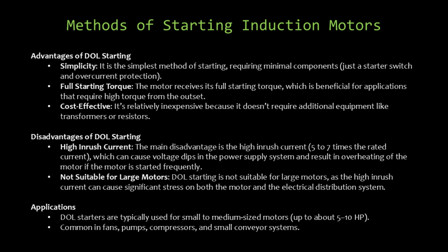However, direct online starting isn't without its drawbacks. The primary concern is the high inrush current, which can cause significant voltage dips in the power supply system. Frequent starts can lead to motor overheating. This method becomes less suitable for large motors, as the substantial current can stress both the motor and electrical distribution system. Engineers must carefully evaluate the motor's size and application.